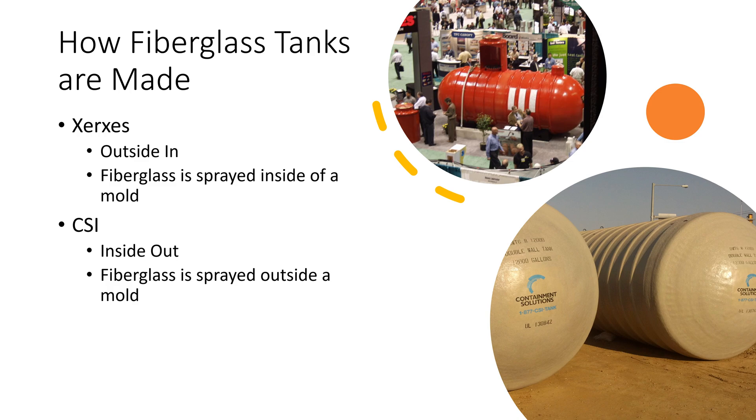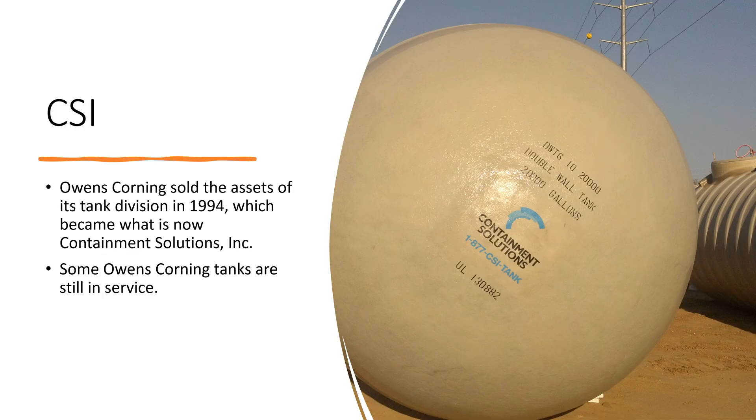Xerxes tanks are made from the outside in — basically someone stands inside the tank as it spins around them and sprays the fiberglass resins on the inside of a mold. CSI tanks are made just the opposite — the fiberglass is sprayed from the outside of the mold and the tanks are formed around the mold. Owens Corning sold the assets of their tank division in 1994, so you'll still find tanks labeled Owens Corning but they're basically Containment Solutions tanks in the ground. When putting a new tank in the ground, pay attention to the end caps — they contain a lot of information. Capturing pictures of these end caps before installation gives you information useful later in the life of your tanks.